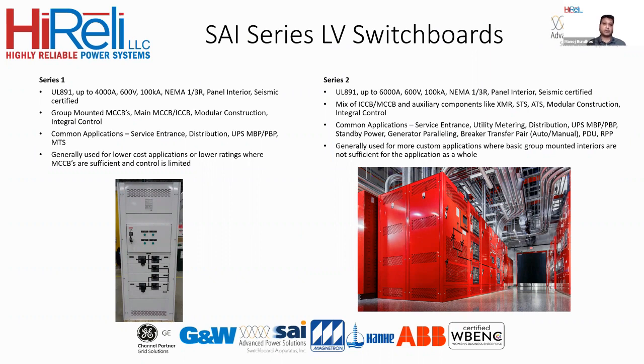On this slide I'll talk a bit about the Series 1 and Series 2. The UL 891 Series 1 goes up to about 4,000 amps, and the Series 2 goes up to about 6,000 amps. Pretty similar applications, but the Series 1 uses more group-mounted molded case circuit breakers in combination with an insulated case circuit breaker as the main service entrance breaker. The Series 2 uses a mixture of insulated case and molded case, with common applications, except the Series 2 is used more for paralleling and breaker transfer applications, and in situations where group-mounted interiors are not sufficient.